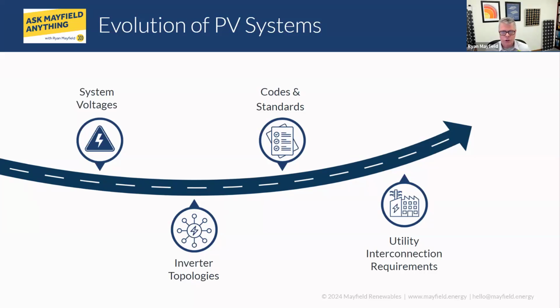We had inverters that utilized a transformer, so the DC and AC sides were isolated across this transformer. Back then we called the systems grounded - we were grounding the DC side. We would typically take the negative, but in some cases the positive side, and bond it to ground with a grounding electrode. 2014 code was all sorts of fun in terms of how you could actually do this, or what the requirements were. The industry has moved away from those.